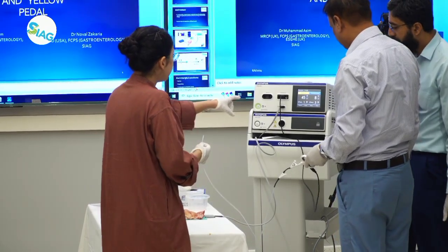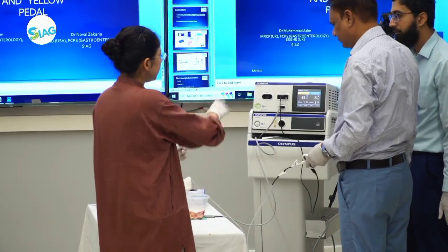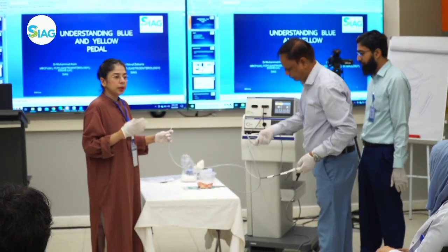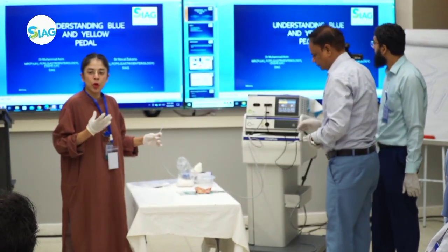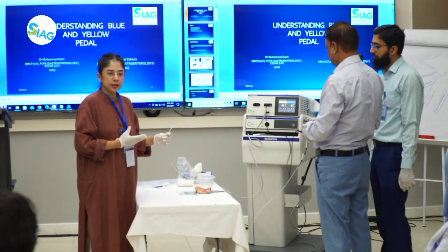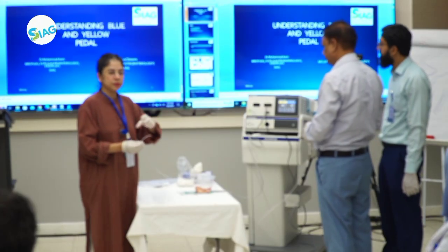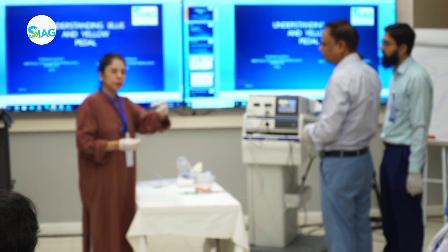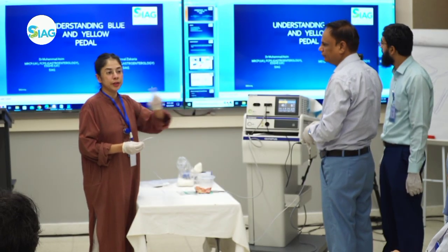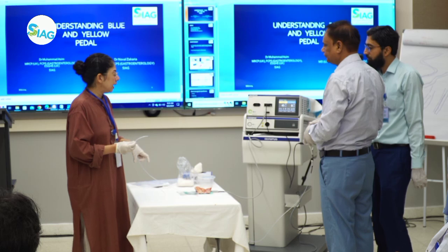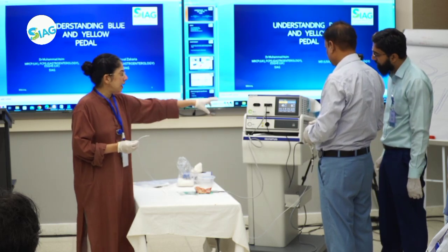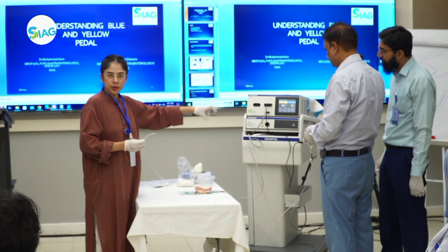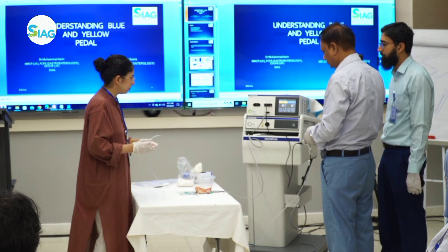Right now it's a standard effect. Okay, so effect 1 is safe. The effect basically determines how much coagulation is inside your cut. So effect 1 basically means there's no coagulation happening. Effect 2 would mean there is some. 3 would mean the intensity of the coagulation is increasing, not the duration of the clot. And so right now we're just going to do pure cut, and we're going to keep it on a high voltage, and let's see how the cut manifests on the chicken.